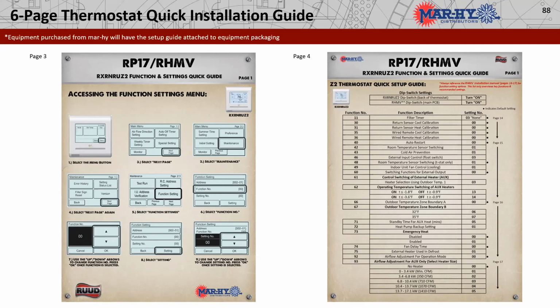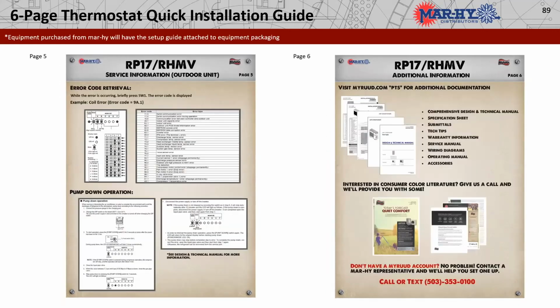Because there are a lot of different formats laid out as to electric strip on, electric strip off. These work as well as the outdoor temperature boundaries, numbers 6 and 7. As you can see, number 6 is 32 degrees, number 7 is 35. So we've given you a range, even though there are 15 different temperature ranges on those settings. What we've done is pick the ones that will work best for this region to make it easier on y'all out there in the field.